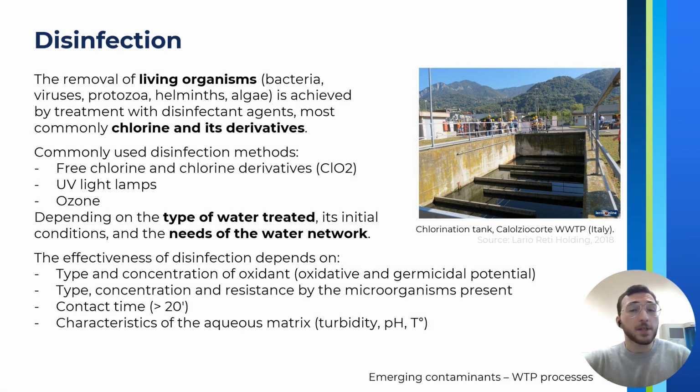Disinfection is an important and common step in the wastewater purification process. During disinfection, living organisms such as bacteria, viruses, protozoa, helminths, and algae are removed by treatment with disinfectant agents. Commonly used disinfectant agents include chlorine and its derivatives, UV lamps, and ozone, with each process providing certain advantages and disadvantages, and the choice being thus down to a case-specific assessment.